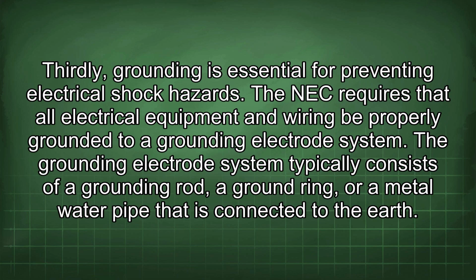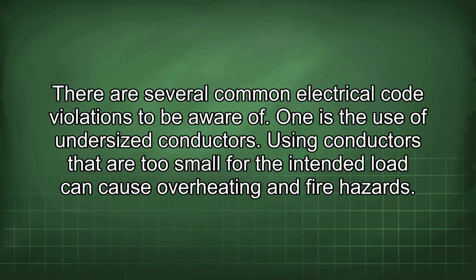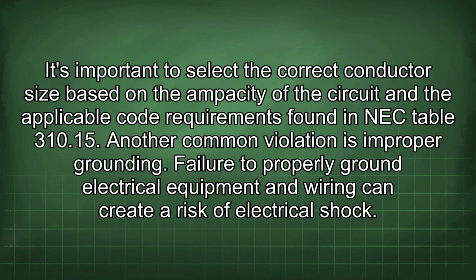The grounding electrode system typically consists of a grounding rod, a ground ring, or a metal water pipe that is connected to the earth. There are several common electrical code violations to be aware of. One is the use of undersized conductors. Using conductors that are too small for the intended load can cause overheating and fire hazards. It's important to select the correct conductor size based on the ampacity of the circuit and the applicable code requirements found in NEC Table 310.15.